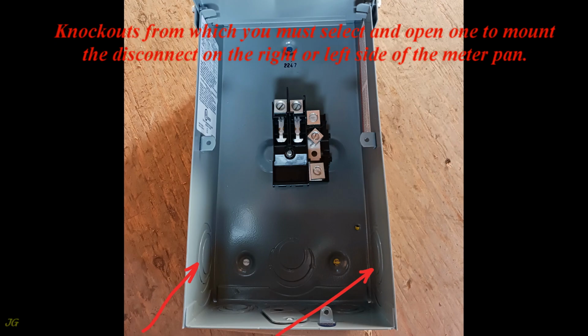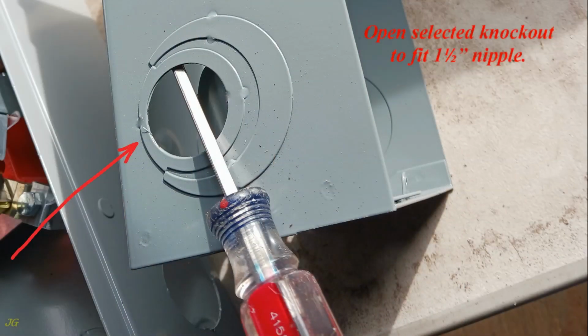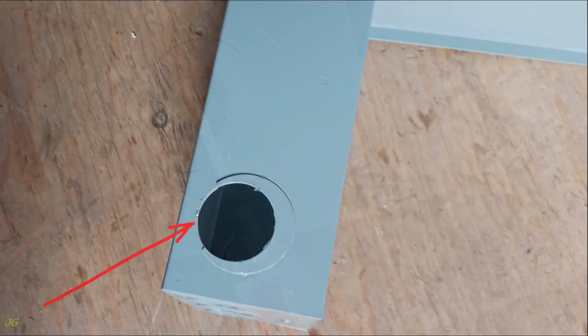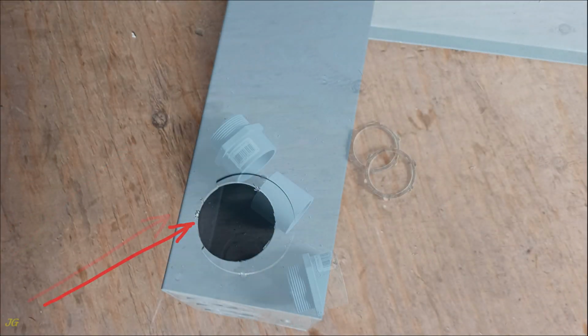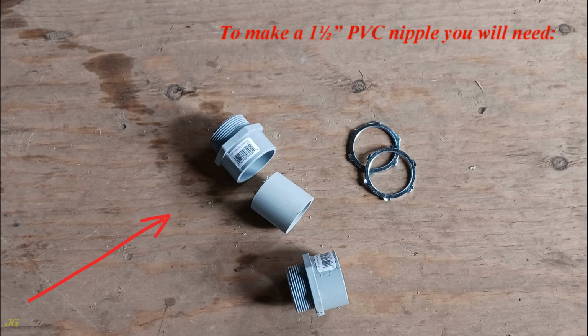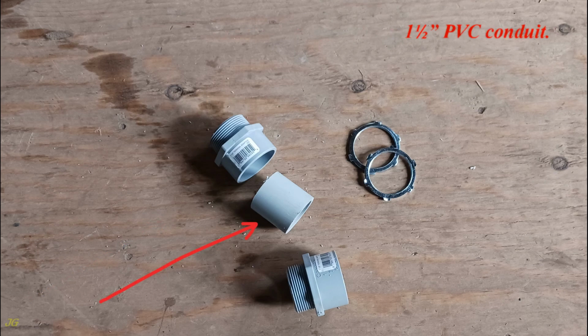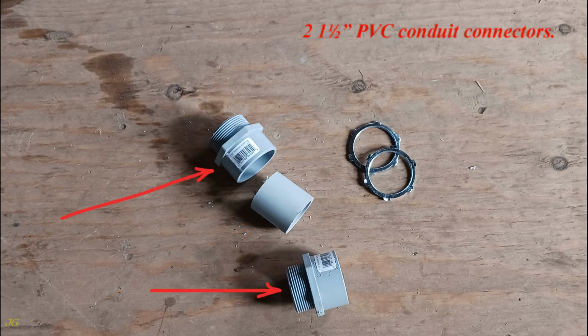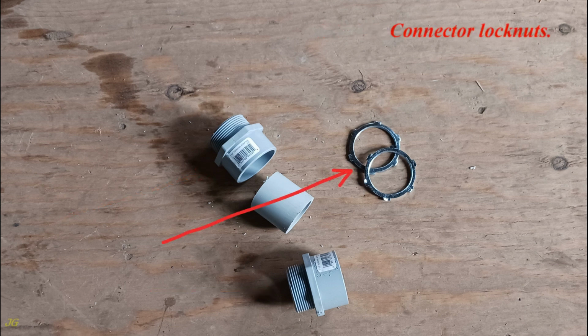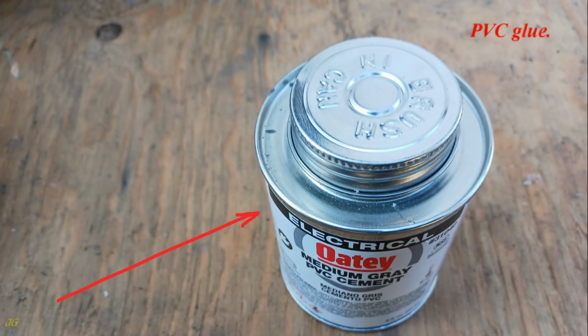Knockouts from which you must select and open one to mount the disconnect on the right or left side of the meter pan. Open selected knockout to fit 1.5-inch nipple. Open knockout. To make a 1.5-inch PVC nipple you will need 1.5-inch PVC conduit, 2 1.5-inch PVC conduit connectors, connector lock nuts, and PVC glue.